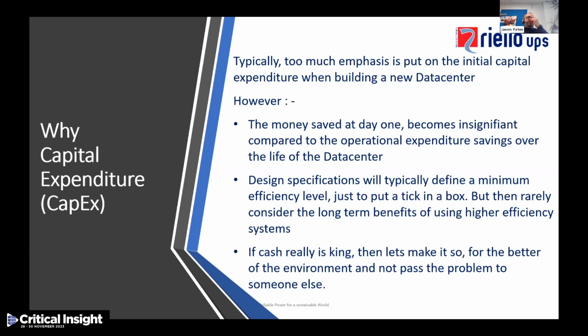Now, the problem we find is that there's too much emphasis put on the initial capital expenditure when building a new data center. However, you've got to agree that the money that can be saved at day one is insignificant compared to the operational expenditure savings over the life of the data center. And we see design specifications will typically define a minimum efficiency level just to put a tick in a box. I'm not saying that everybody does, but they rarely consider the long-term benefits of using higher efficiency systems. So if cash really is king, then let's make it so, but for the better of the environment, and not try to pass the problem on to somebody else.